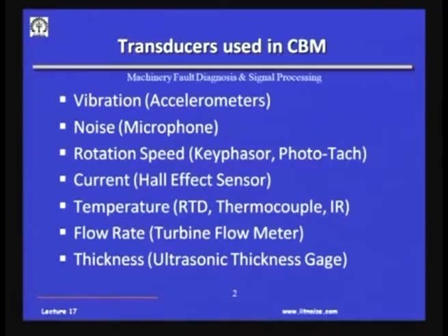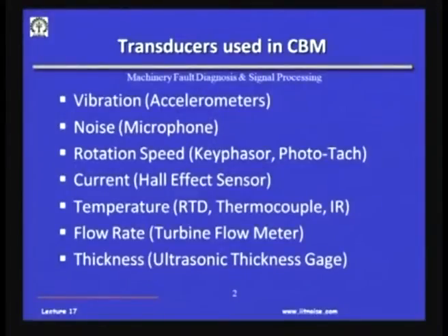There is scale deposit and the thickness increases. So, the effective diameter of the pipeline for flow reduces, and this can be measured by techniques like radiography or ultrasonic thickness gauge. And another important application of ultrasonic thickness gauge, which I had told earlier also: suppose there are internal cracks in the structure which cannot be seen visibly from the outside. So, if we have an ultrasonic probe, it can be used to detect the presence of the crack.